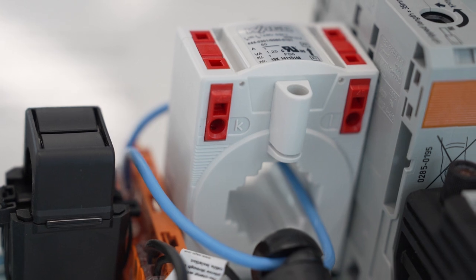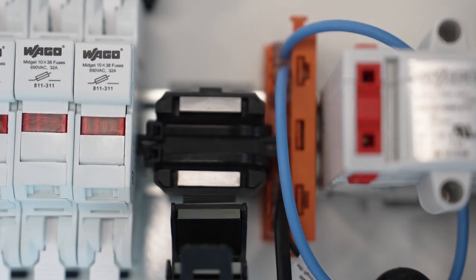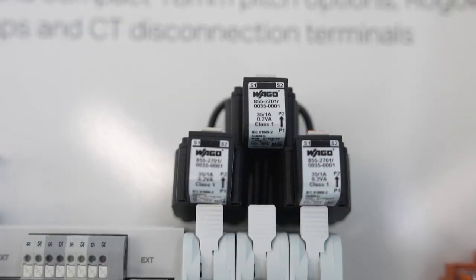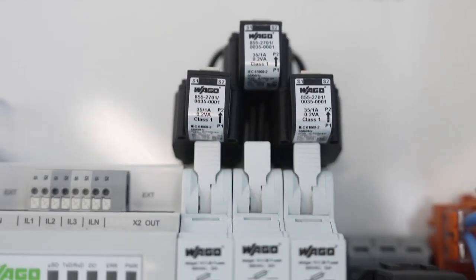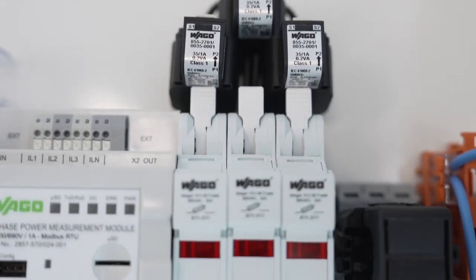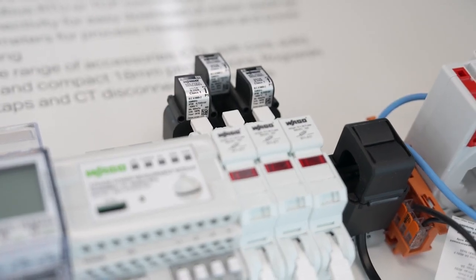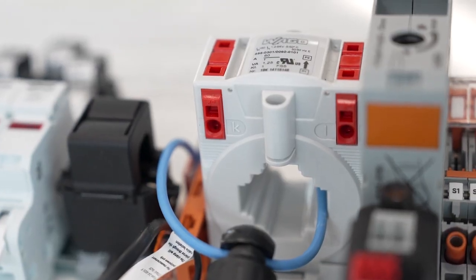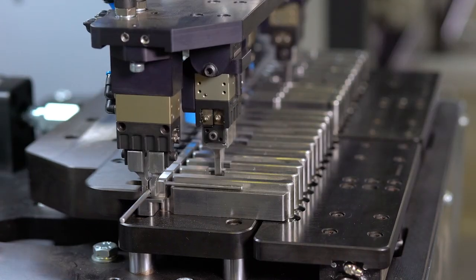WAGO offers both solid or split core versions, or an ultra-compact 18mm pitch version for close mounting adjacent to your MCBs. Whether you're retrofitting or building new systems, there is a perfect solution, irrespective of the space available or design of enclosure. In short, if you're looking for dependable, accurate measurement technology tailored to your needs, WAGO's current transformers are a smart and trusted choice.